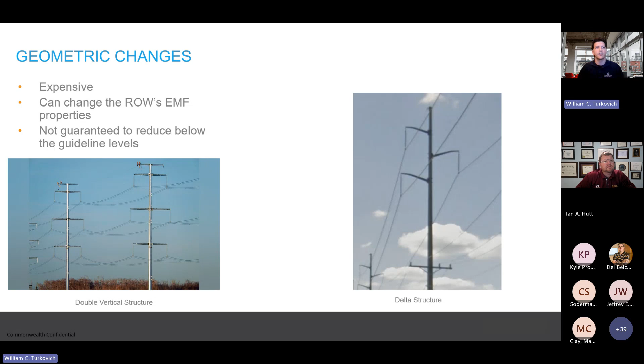Ian will pick up the next slide. Sure. So the geometry is a big play on how the phases interface with each other, and it's always a balancing game. You have minimum spacing required for open outdoor air insulated conductors, so there's only so far away or so close that you can keep these conductors, and that arrangement is important. Generally, if we can get the conductors a little bit closer together, sometimes you can have cancellation effects that can greatly help you on the EMF side.